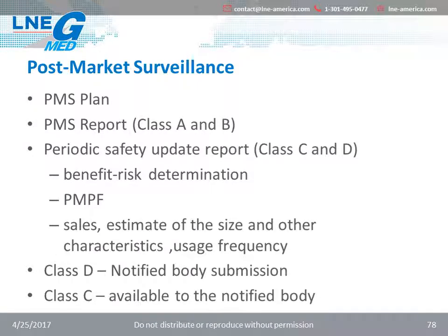The post-market surveillance system must be based on a post-market surveillance plan, which will be part of the technical documentation. Manufacturers of Class A and B devices must prepare a post-market surveillance report summarizing the results and conclusions of the analysis of the post-market surveillance data gathered as a result of the post-market surveillance plan. This must also include rationale and description of any preventive and corrective actions taken. The report needs to be updated and made available to the notified body and the competent authority upon request.